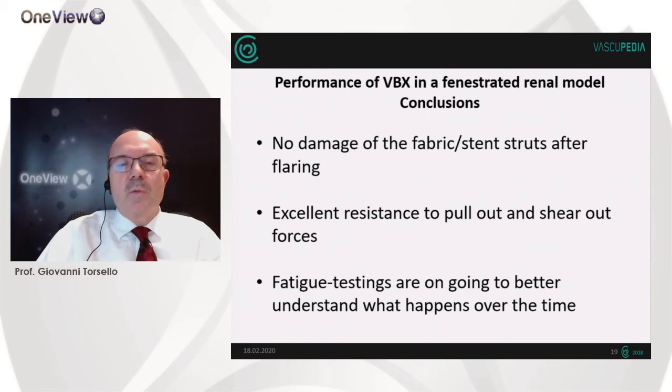So in conclusion, we didn't observe any damage of the fabric or of the stent struts after flaring. We found an excellent resistance to pull out and to shear out forces. And now the fatigue tests are ongoing, but we have to wait for 25 million cycles to better compare the resistance of the different bridging stents used for this indication for fenestrated and branch grafts.